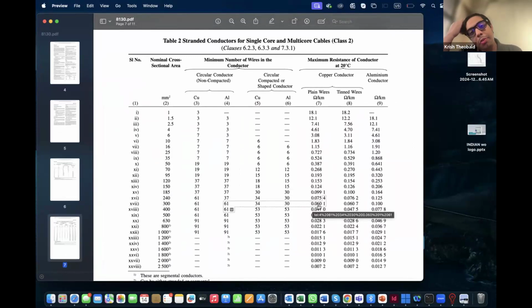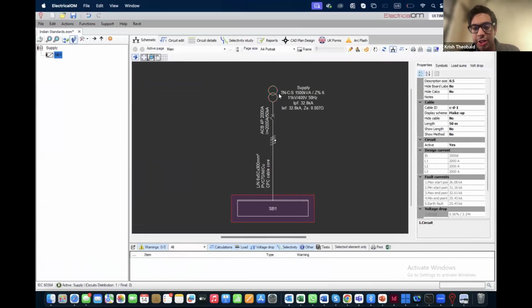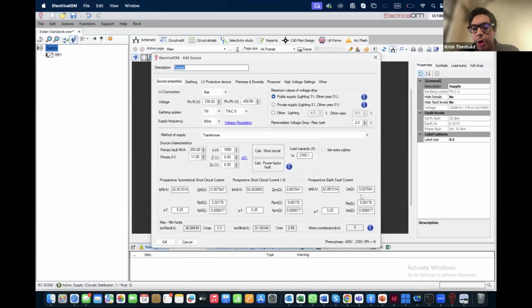But the truth is that the impedance is made up of a resistive component and a reactive component. If we model a situation like this, where we have a supply with say 32.8 kiloamps of short circuit current available at the source, with an impedance of 0.007 ohms, it's not really 0.007 ohms, because this is broken down into a resistive component, which is very little, only 0.00176, and a much more major reactive component, which is 0.006817. This has been calculated for a particular arrangement with a 1500 kVA transformer.